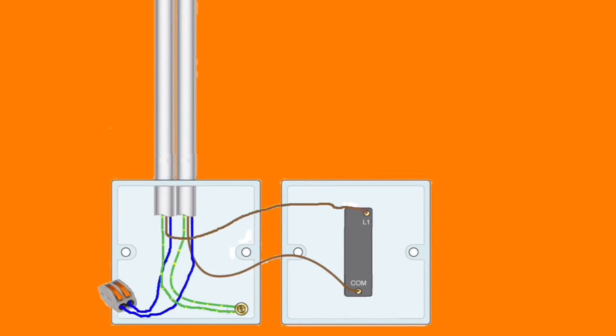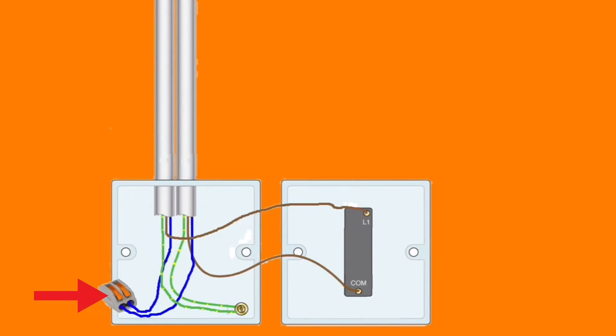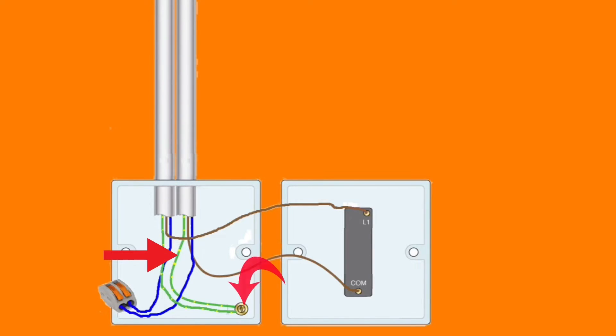The cable bringing in the supply brings a brown permanent line connection which is connected in this case into the common terminal, and also a neutral which is into a connection. This is a maintenance-free connector block in this diagram, and also the CPC which is secured in the earth terminal, in this case in the back of the box.